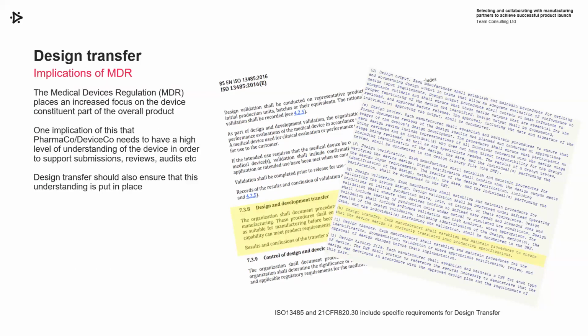There's one particular implication from the MDR, which is more emphasis on the device constituent part of an overall product, where you have maybe a combination product, where previously the most focus might have been on the drug side. There's a lot of emphasis on the device side now. One implication of that is that Pharmaco, Medical Device Co, needs to have a good level of understanding of that device to manage submissions, support submissions, reviews, audits, lifecycle management, etc. So the design transfer process needs to ensure that that understanding is put in place.